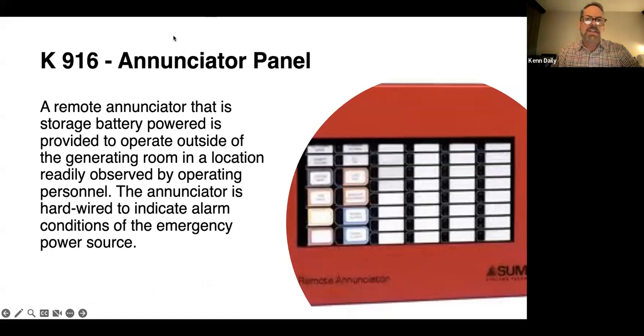The annunciator panel for the generator must be at a manned location, observed by operating personnel. Most of you should have already moved these over the years, but I still see this citation. It's probably going to be at a nurse's station. It can't be in a mechanical room. It can't be at a reception office, because reception is not there 24 hours a day. If you're large enough, it could be at a security office. If you're a CCRC or you have multiple levels of care, you may have a security office that's manned, and that's fine. But most skilled nursing homes are going to have it at a nurse's station.